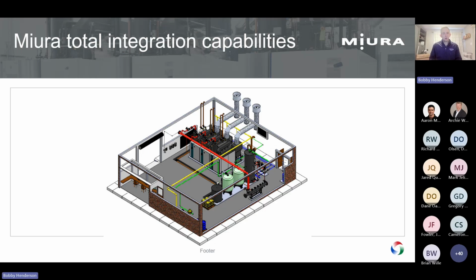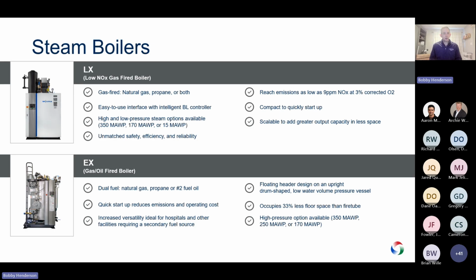Miura takes control of the whole boiler room. That's another really nice feature here. They'll provide you not just the boilers, but we're going to provide the water softeners, chemical treatment, and all the controls that are going to talk to everything in the boiler room. So again, this is the LX boiler up on the left. They also have a dual fuel model, which is their EX. Similar type of design, but built for dual fuel. They also have low NOx options with that.